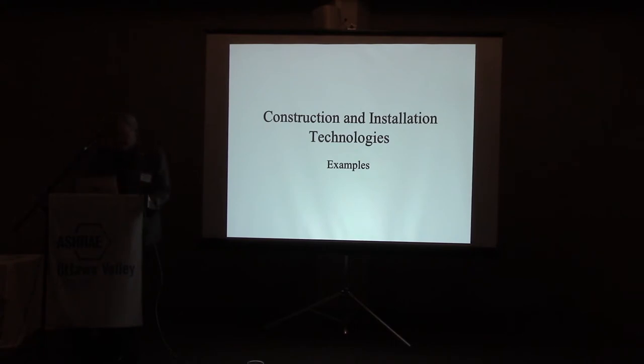So now we go into some examples. One of the critical issues when you have to install in the concrete slab in the building is that the HVAC has to be involved from the beginning. You cannot install the system after the building is made, because you have to get pipes in the slab. If you have a suspended ceiling or floor heating, then you don't have to be there from the beginning. And the installation of suspended radiant cooling panels or floor heating is well known from the manufacturer, so that's not really an issue. But if you want to have piping in the concrete structure, you have some issues.